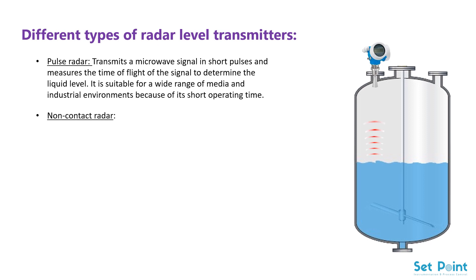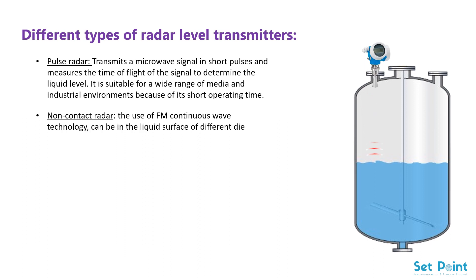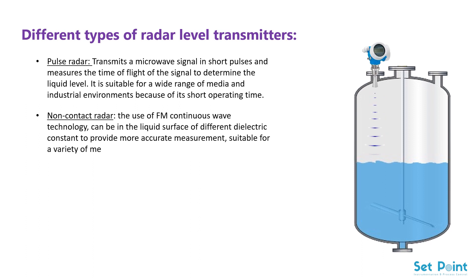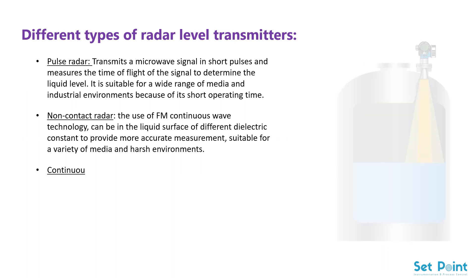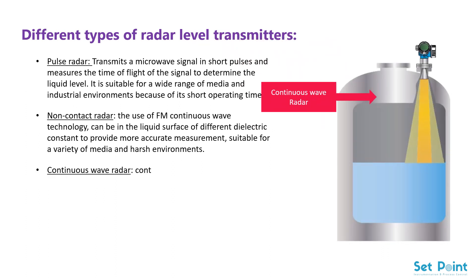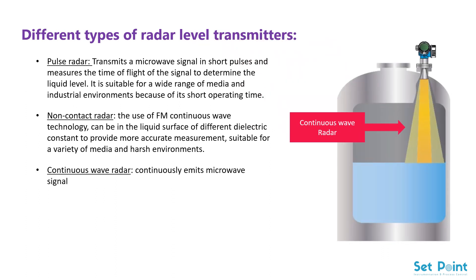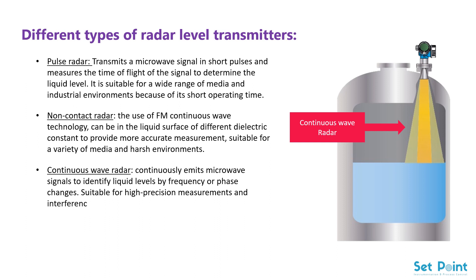Non-contact radar uses FM continuous wave technology and can provide more accurate measurement across liquid surfaces with different dielectric constants, suitable for a variety of media and harsh environments. Continuous wave radar continuously emits microwave signals to identify liquid levels by frequency or phase changes, suitable for high-precision measurements and interference-prone environments.